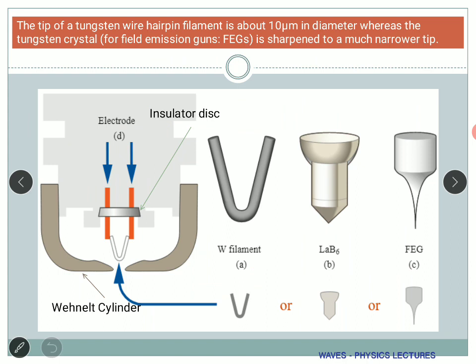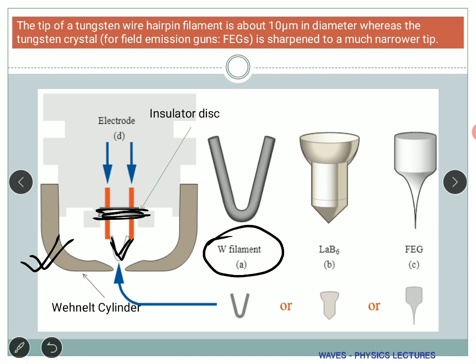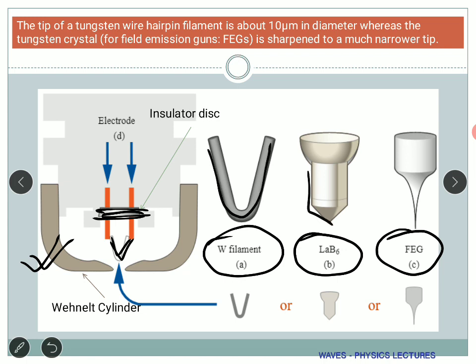This is a typical simplified diagram of an electron gun with an anode and a cathode. The Wehnelt cylinder is visible, along with an insulator disc and the tip — the material from which electrons are emitted. This material might be a tungsten filament, lanthanum hexaboride, or a field emission gun. There is a difference in design: tungsten is roughly V-shaped, and the field emission gun has a very sharp tip, so the electrons generated are fewer and more focused.